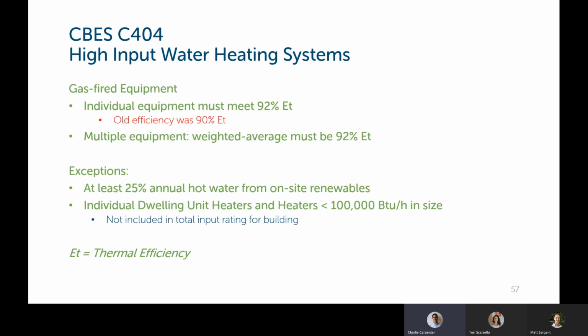You don't need to meet those efficiency requirements if at least 25% of the hot water demand annually comes from on-site renewables, or if you've got individual dwelling units that have their own individual hot water heaters, and those heaters are less than 100,000 BTU per hour in size, you don't need to include them in the larger building scale high input water heating systems. You don't need to include those in the calculation up above.